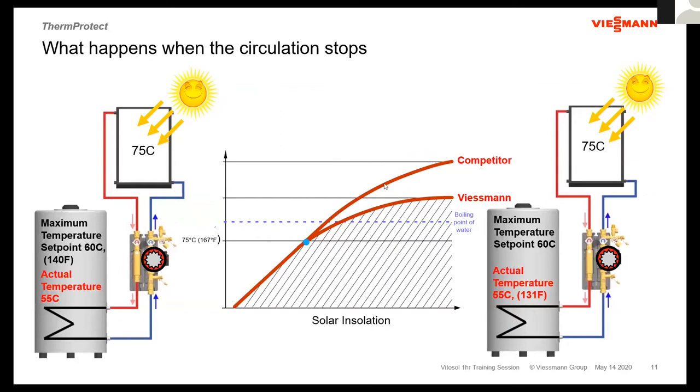We've got our collector sitting here. This is just a domestic hot water system. You've got a temperature in the tanks here of about 130 Fahrenheit, about 55 C. The set point is 140 or about 60 C. And I use the 75 C here as a baseline, but typically in operation, if we're at this temperature, we're pretty close to achieving this set point. If the temperature of the tank was down in the 30s, then this collector temperature would actually be quite a bit lower as well. As we pull that heat in and the temperature rises in the tank, so will the average collector temperature as we move through here. So we're at about 75 C here, about 167 degrees Fahrenheit at this particular point.